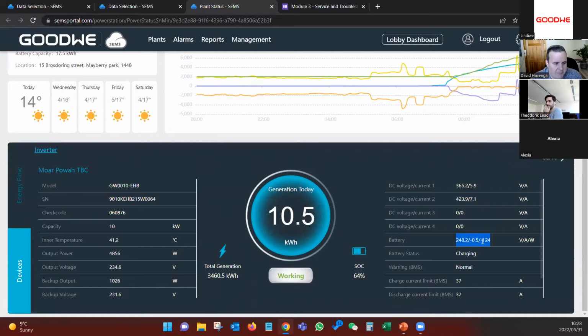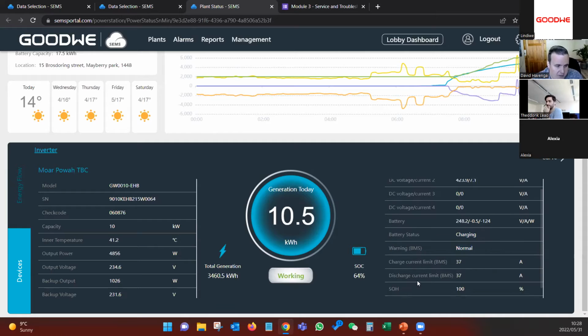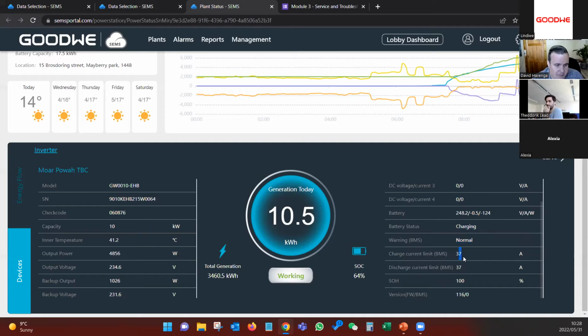You can see the battery information, so the voltage of the battery, the current draw, the wattage draw or charge, the status, whether it's charging, discharging, or in a fault mode, if there's any problem with the battery, BMS warnings, so what is the BMS telling the inverter, as well as the charge current limits from the BMS. So these charge current limits are dynamic from your BMS. So if you aren't seeing a value here that you are expecting, especially on low voltages, you'll see the current will increase quite a bit depending on the modules you add to the inverter.